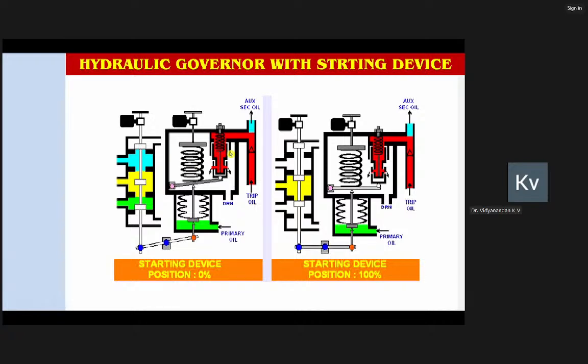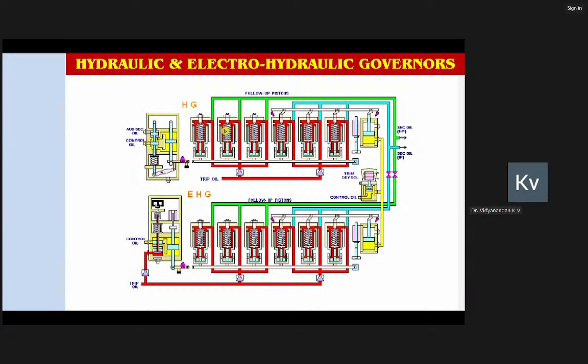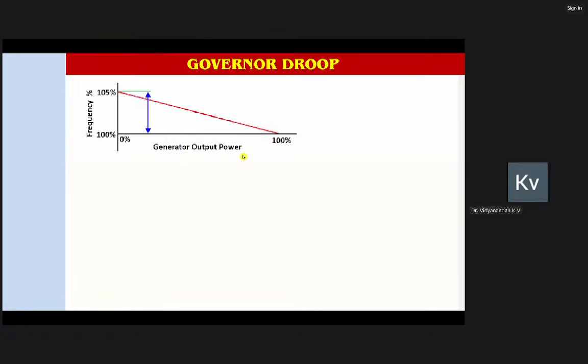That means the oil which is required for opening the control valves, in your case, that is what you call the secondary oil, will drain completely, and thereby all the control valves and the stop valves will close. That is what turbine trip. So the starting device has a very significant role to play as far as the initial activities are concerned, even during normal running also. Now, because KWU turbines have both the hydraulic and electro-hydraulic governors, these two are joined and interfaced to a common link, and finally we get the secondary oil pressure.